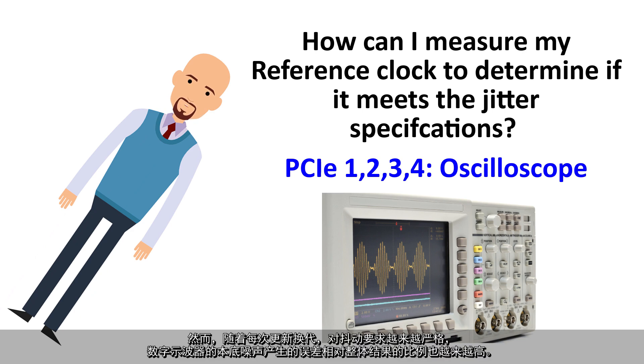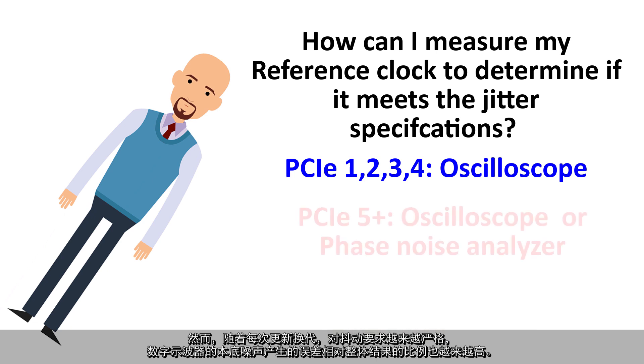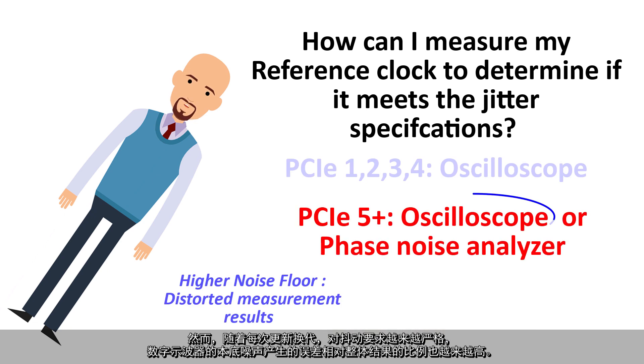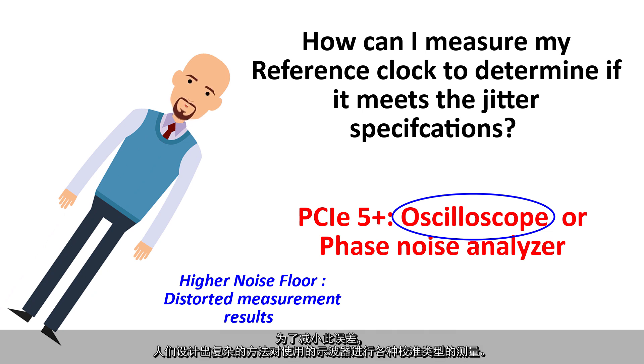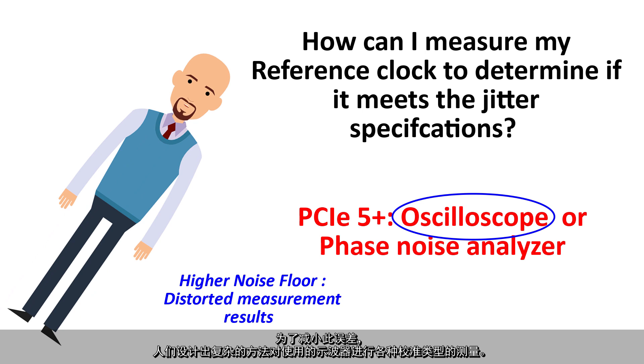As the jitter requirements have gotten tighter with each successive generation, however, the noise floor of digital oscilloscopes has been adding increasingly more error relative to the overall results. In an attempt to attenuate this error, complex methods have been devised to take various calibration type measurements with the oscilloscope being used.